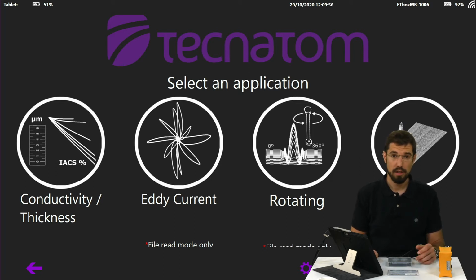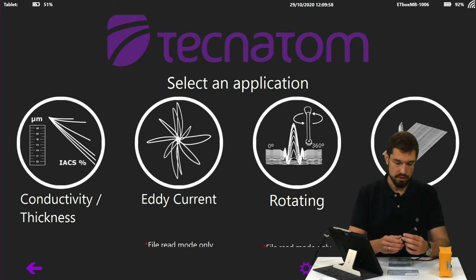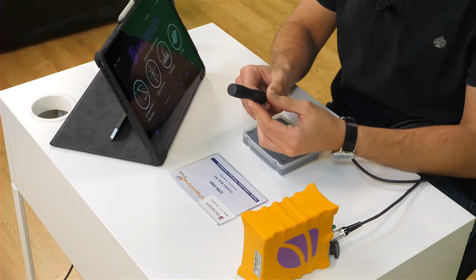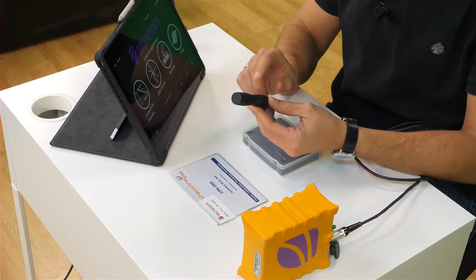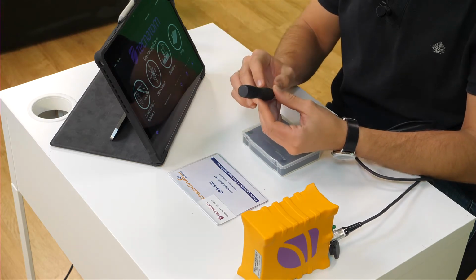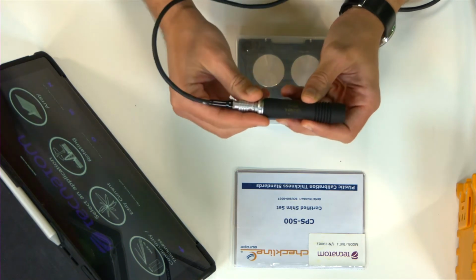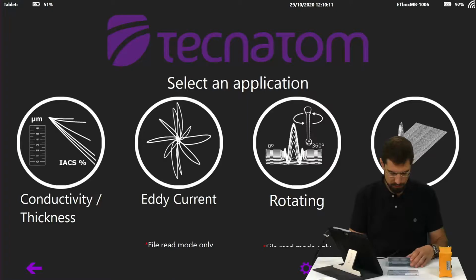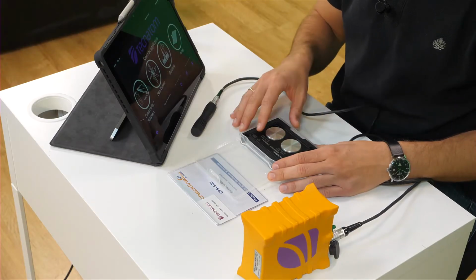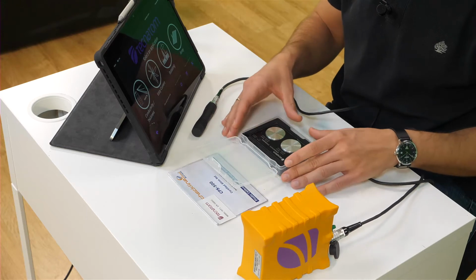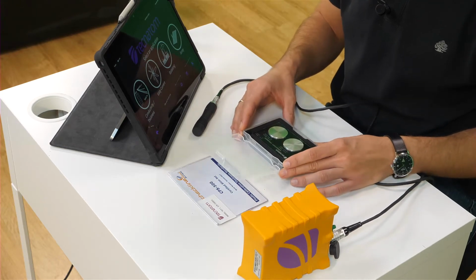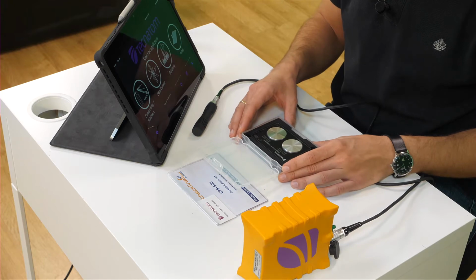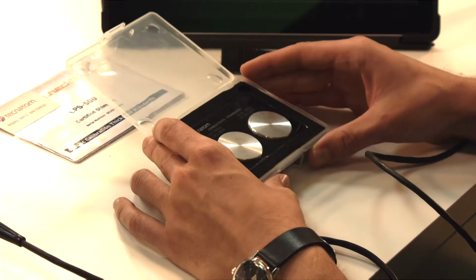Let's see an example using this probe, especially developed to measure conductivities. As we can see, the probe has a small LED that lights up with the alarm that we can set up, and it's a probe that works at 60 kHz. For this demonstration, we also have 2 conductivity measuring blocks. In this case, these are 2 aluminum blocks that have their own certificate. These blocks are manufactured and certified by Tecnatom to calibrate the conductivity test.